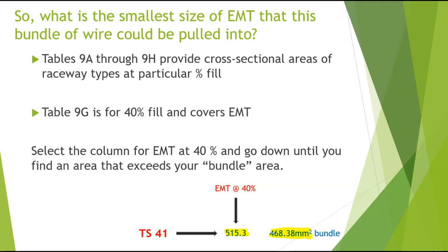All we have to do then is go across in that row and see that this is associated with trade size 41 EMT. And we can be confident because this trade size 41 EMT has a cross-sectional area of 515.3 square millimeters at 40% fill, that we will be able to fit our bundle, which was only 468.38 millimeters squared, into this raceway.